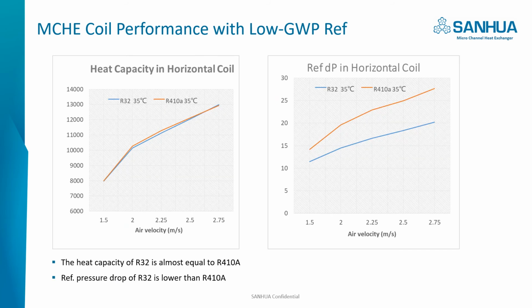Here is the result of the microchannel coil performance with low GWP refrigerant. First, on the horizontal coil, we present the heat capacity and also the refrigerant pressure drop, comparing R32 and R410A. The left chart shows that the heat capacity of R32 is almost equal to R410A. The right chart shows that the refrigerant pressure drop of R32 is lower than R410A because the mass flow of R32 is lower.